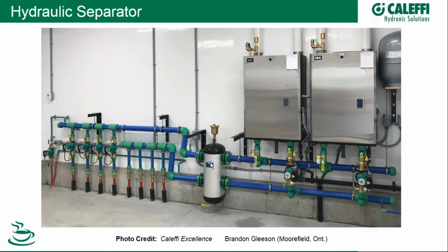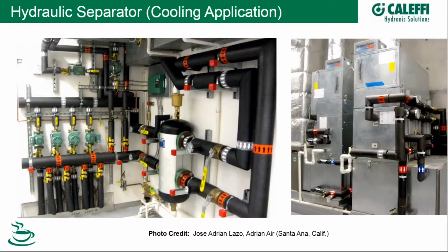Now, it's not just heating where you need to worry about pumps interfering with one another. Chilled water applications have the same requirement. And here's a job from Mr. Jose Adrian Lazo out at Santa Ana from Adrian Air. We were happy to have him submit this. It's actually a 4-pipe system, so he's got heating and cooling. He's got Unico fan coils over here. You can see some really good attention to detail on his piping as well as his insulation.